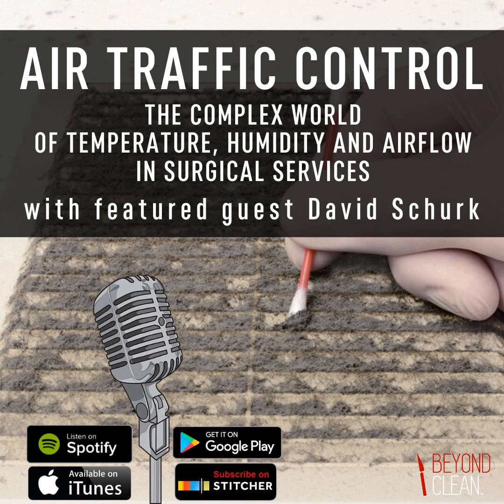So the same thing can happen in an operating room where the room itself has been air conditioned and all the surfaces within that operating room have been chilled to a certain temperature. And then something goes wrong with the operating room HVAC environmental control system, or the controls, or the actual ventilation system, or something of that nature, where air enters the space that is warmer and moister than it should be.